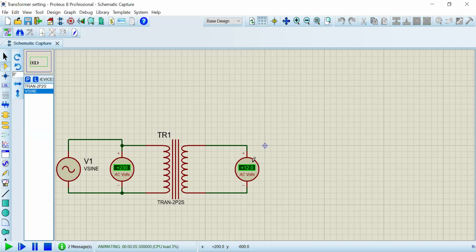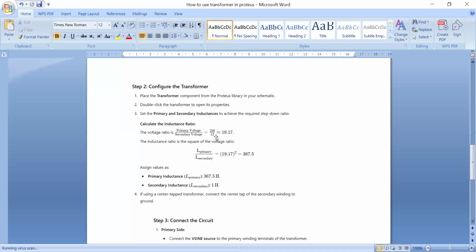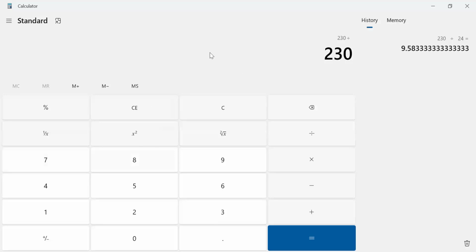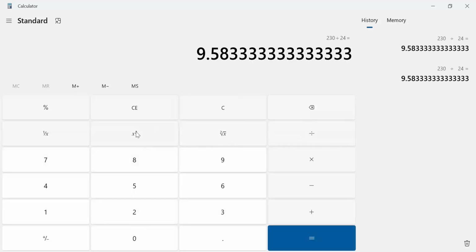Now, if you want 24 volts, where must I change this? I must go here: 230 divided by 24, then square the result and adjust it. I'll click on the calculator. 230 divided by 24 equals, and I square it: 91.84, to set in the primary winding.